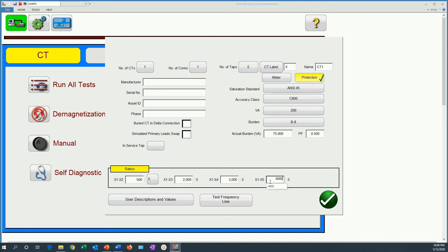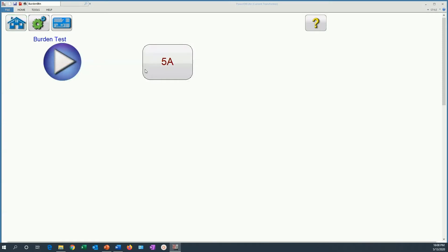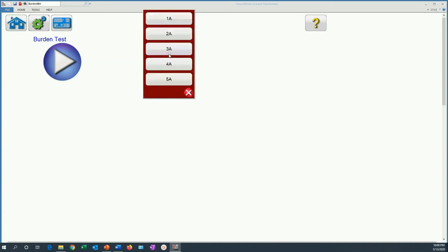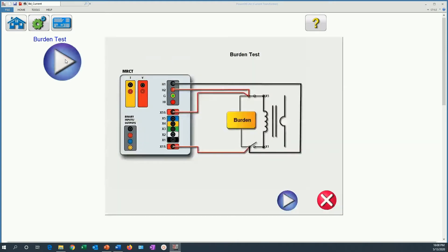And then we can proceed to the actual test to select the burden test. We click here. Now remember that the burden test should be run at the nominal current of the CT that we are testing. In this case we selected, we are going to select the 5A CT. Now when we click here, the burden test, we are presented with the connection diagram.